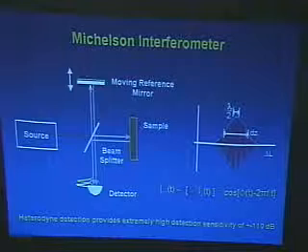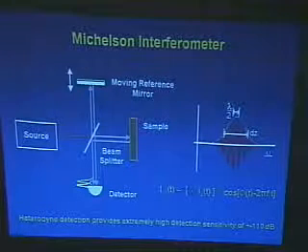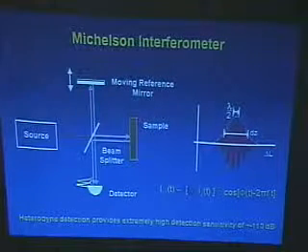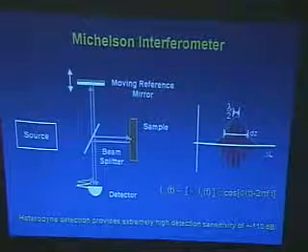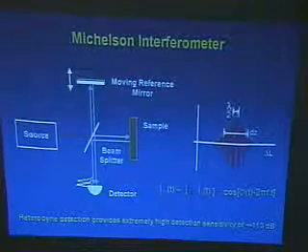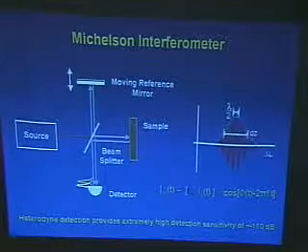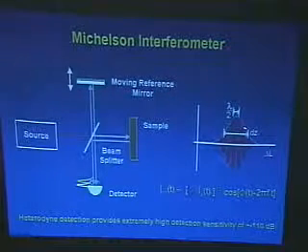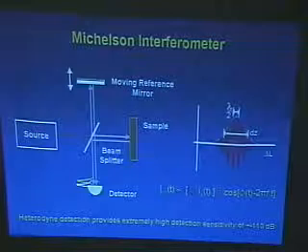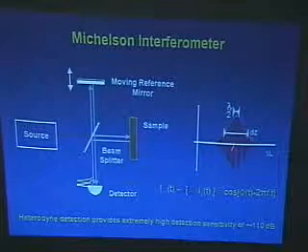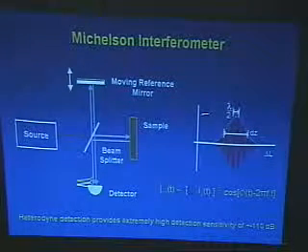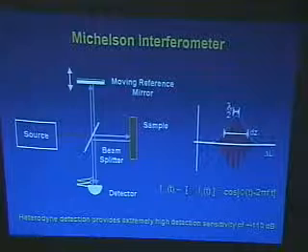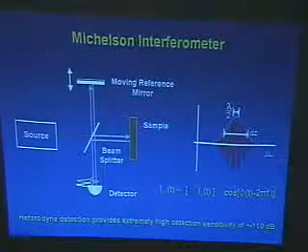By moving this mirror back and forth, you change the reference path length, and you can pick up the pulses from the sample back-reflected at different depths. If you look at the OCT signals, the interference signal is shown here. It's more or less like radio frequencies, an amplitude modulated signal. It's isolated, and the full width at half maximum of this signal gives you the so-called depth resolution.